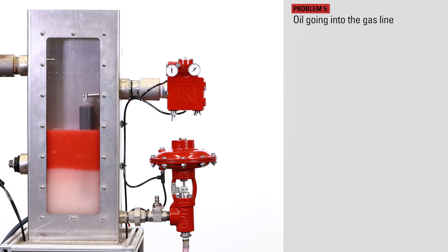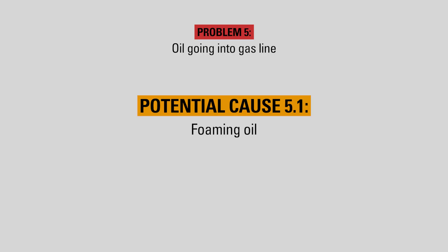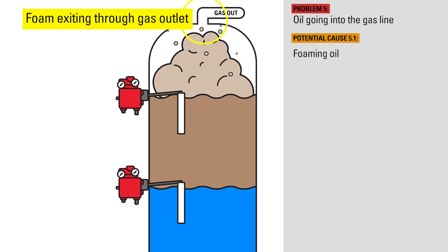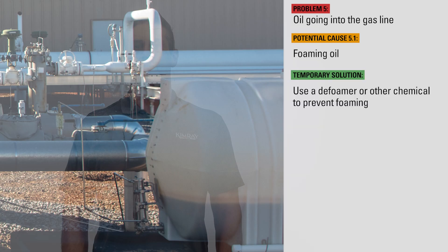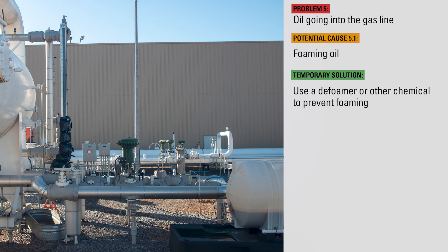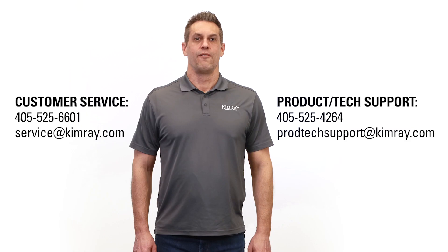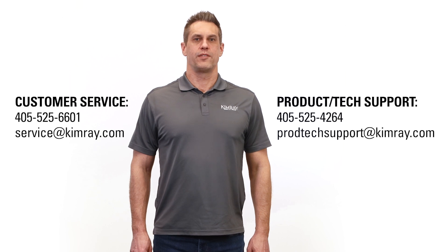If the oil level in your vessel seems to be maintaining at the desired level within the sight glass range, but somehow oil is making it into the gas outlet line in the vessel, you may have an issue of foaming oil. Foaming oil is not dense enough for the displacer to sense its level inside the vessel. The displacer senses the actual liquid oil level, so if the foam continues to rise, it could eventually exit the vessel through the gas outlet line. You typically won't see an indication of foaming oil in the sight glass because it's only happening inside the vessel. Defoamers or other chemicals can be used to help prevent foaming, but are just temporary solutions. The cause for the foaming could be that there are contaminants in the oil flow stream. For further help, contact the experts at your local Kimray store or authorized distributor.